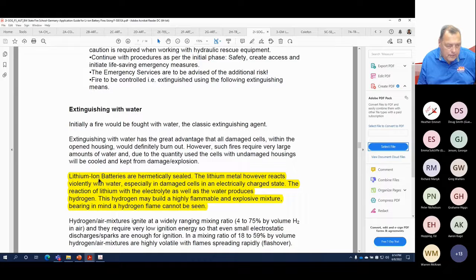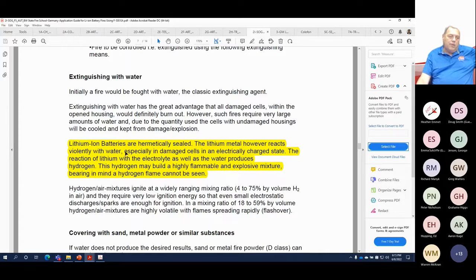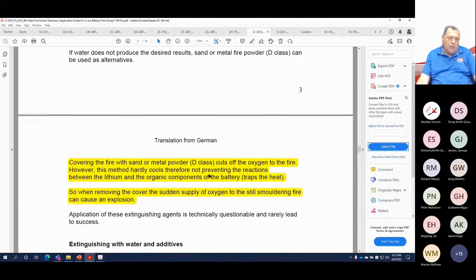Here they talk about batteries and extinguishment with water. Lithium-ion batteries are sealed. The lithium metal, however, reacts violently with water, especially in damaged cells that are in an electrically charged state. The reaction of lithium with the electrolyte as well as water produces hydrogen. This hydrogen can build up highly flammable and explosive mixtures, bearing in mind, hydrogen flames cannot be seen. So some of this came from the Bosch testing on lithium-ion battery with plain water. The issue there is they sometimes get a reaction depending on the chemistry of the battery, and as we know, it takes copious amounts.